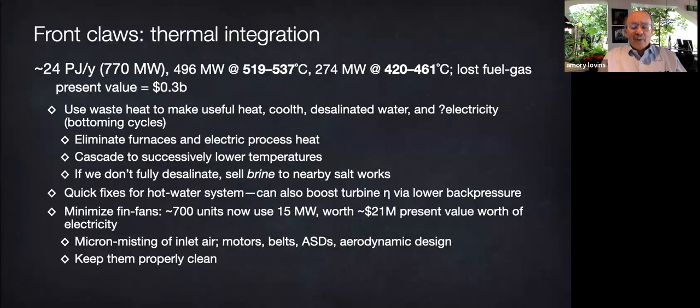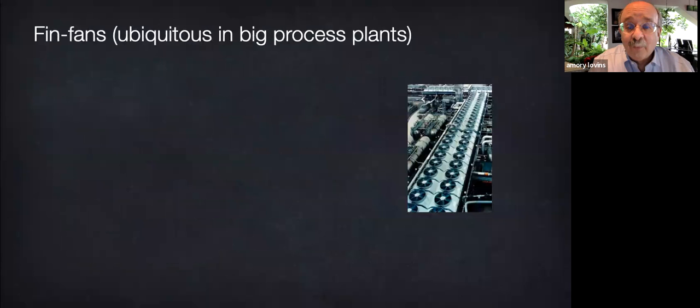You might wonder, how do you throw away that much heat, 3/4 of a gigawatt at high temperature? Well, with 700 fin fans that used 15 megawatts of electricity just to spin their fans, that was $21 million worth of electricity, present value. And the fin fans could be run much better, but we had other ideas.